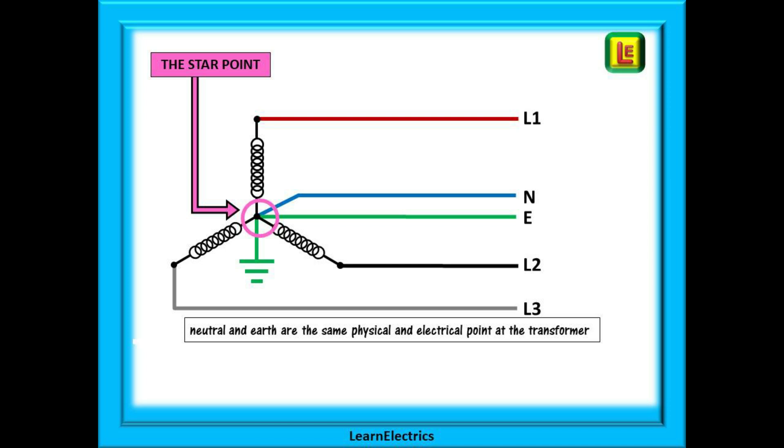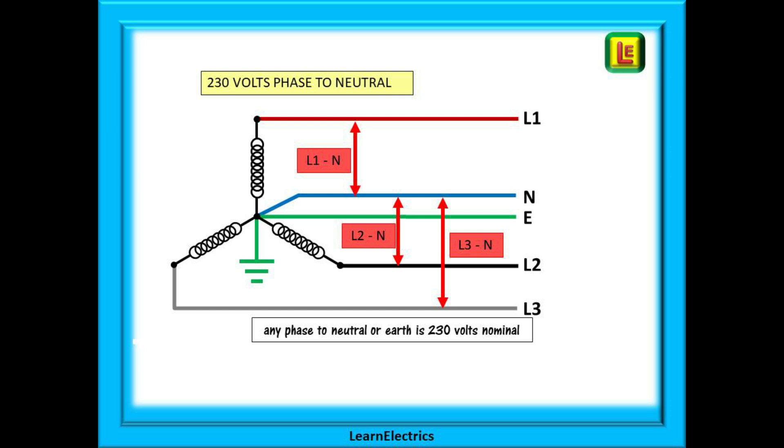How the earth and neutral arrive at the property after they leave this point will determine if the system is TNS, TNCS or TT. If we measure from any phase to the neutral we will get 230 volts nominal. L1 to neutral, L2 to neutral, L3 to neutral, each will be 230 volts. A measurement between a phase and earth will be 230 volts also. Neutral to earth should always be 0 volts.